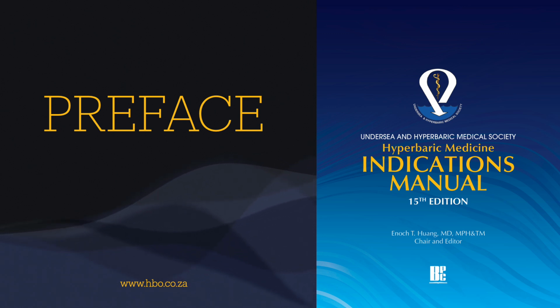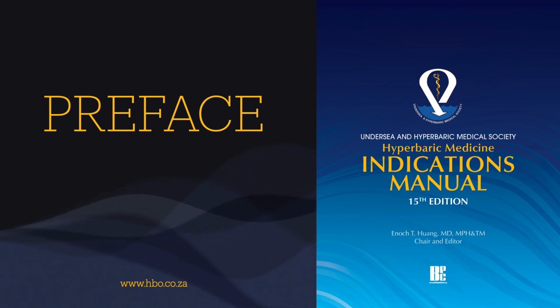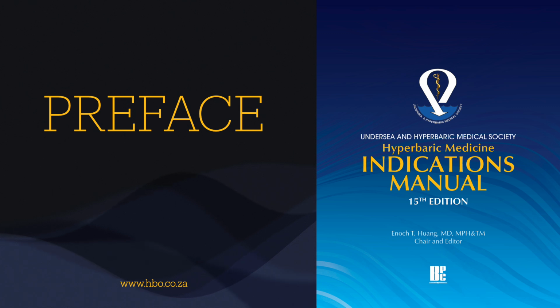And that chamber needs specific certifications. Absolutely crucial. The manual requires the chamber to meet the American Society of Mechanical Engineers Pressure Vessels for Human Occupancy code. That's ASME PVHO-1. What does that cover? That code governs the structural integrity and safety of chambers designed to operate under pressure with people inside. It's a vital engineering standard. Additionally, the chamber must meet the National Fire Protection Association NFPA 99 code and standards for hyperbaric chambers. NFPA 99 for fire safety. Makes sense, given the oxygen environment.